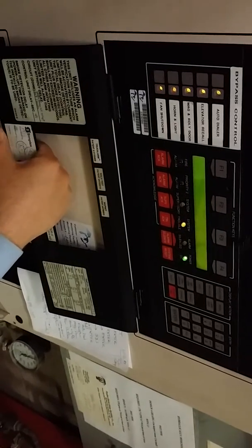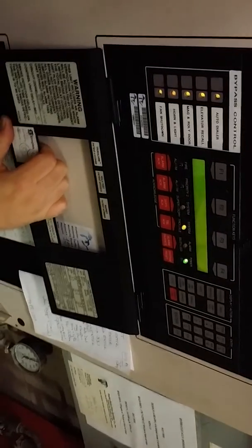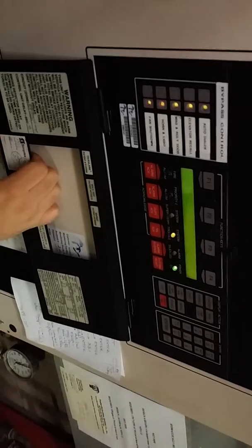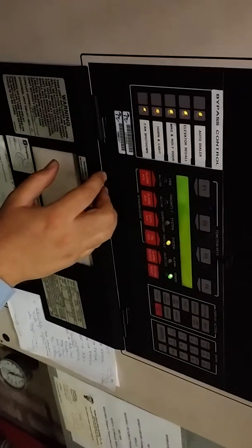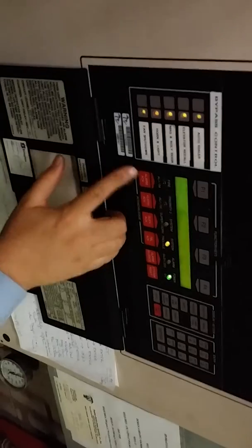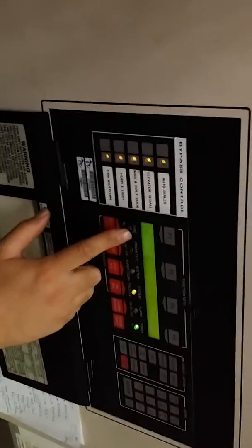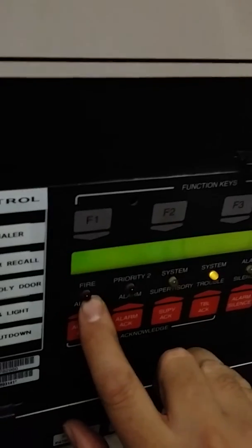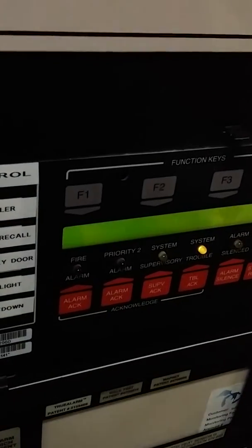And so what I want to show you now is what you need to know to access this very thing. If you were to have a fire alarm here, this red light would be blinking or lit up. Blinking would mean that the fire alarm hasn't been acknowledged yet. You'd also hear it going beep, beep, beep. The trouble does a solid beep, a buzzer on it.